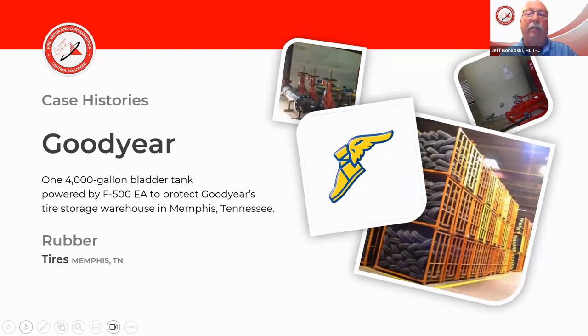After doing some testing with F500, we are now protecting GM's battery abuse lab. Goodyear in Memphis wanted to save money. They had a warehouse where, due to limitations on the number of racks they could have, they had to rent additional warehouse space. They were trying to see if they couldn't go one rack higher so they wouldn't have to keep renting that additional space. Testing took place, looking at F500 and working with the authority having jurisdiction, the fire department. Based upon the testing and the ability of the F500 encapsulator agent to cool and extinguish, they allowed, with the introduction of F500 into the fire protection system, Goodyear to go one rack higher on their storage.